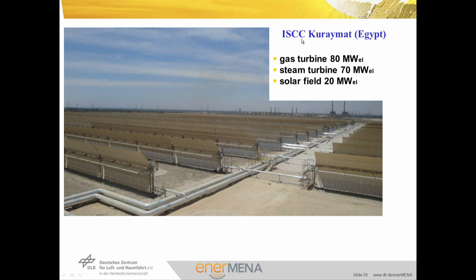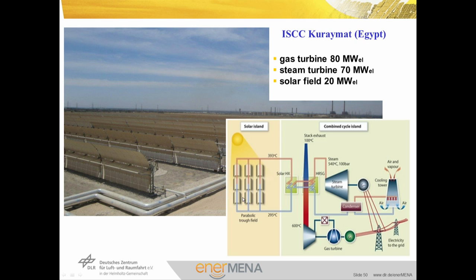The ISCC Kuraymat power plant in Egypt uses integrated solar power into combined cycle. A gas turbine of 80 megawatt electrical power and a steam turbine of 70 megawatt electrical power are used, with 20 of the 70 megawatts produced by the solar field. The gas turbine exhaust gas goes to a heat exchanger to produce steam for the steam turbine, and the solar field also connects to this heat exchanger to contribute heat for steam production.